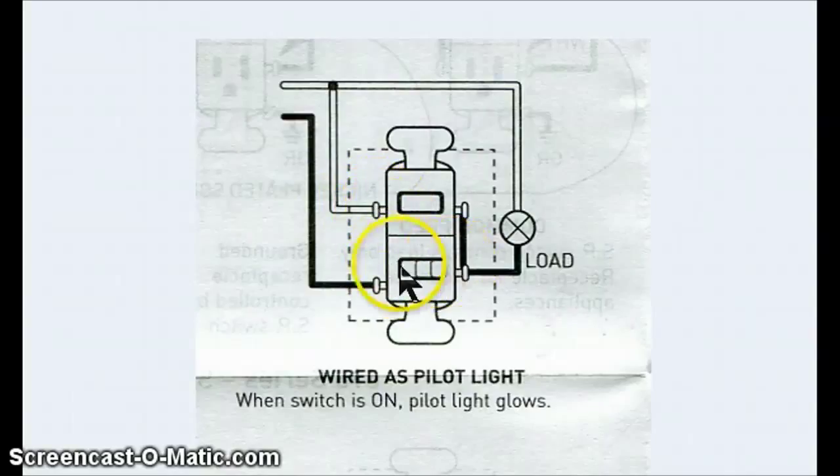On the other side of this switch, activated by this switch, we have these two brass screws. They are the same electrical point because they are strapped internally together. They show a strap here, which is external, and you could put that there. It wouldn't hurt anything. But the fact is, this thing is already strapped.